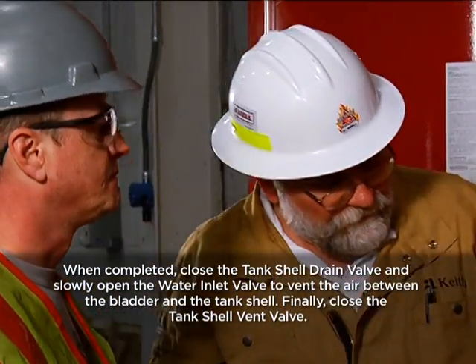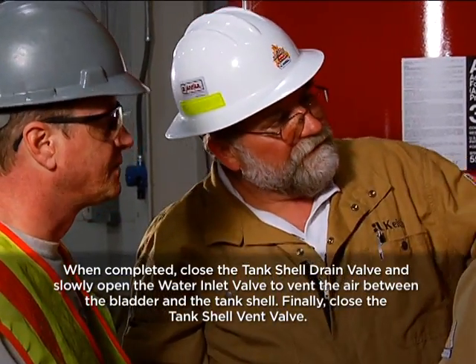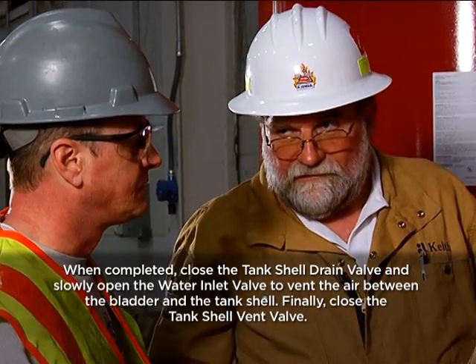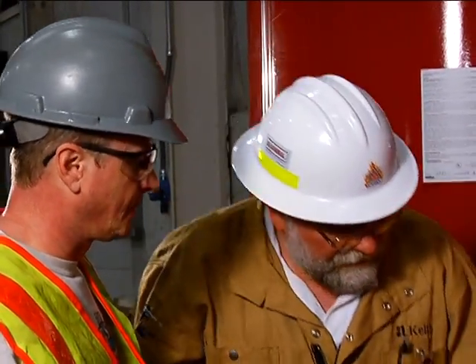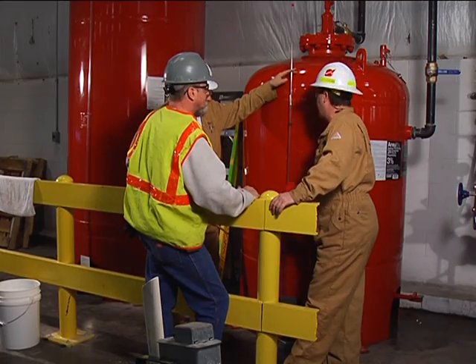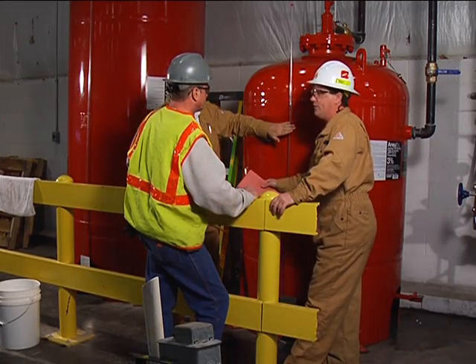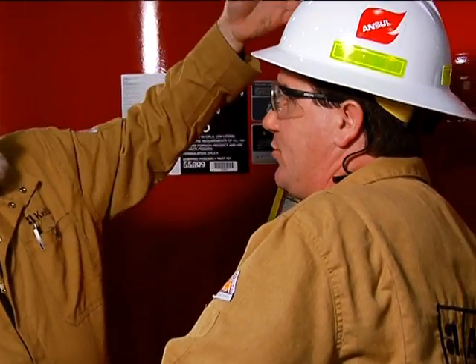Because with some types of foam concentrates, now this one goes up the sight gauge freely, but there's some types of foam concentrates that are thick, more viscous. And the liquid level goes up so slowly up the sight gauge tube that you don't get an accurate reading. And so then we don't even put one of these on. We don't even recommend a sight gauge in that case.